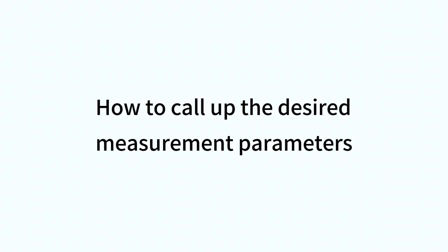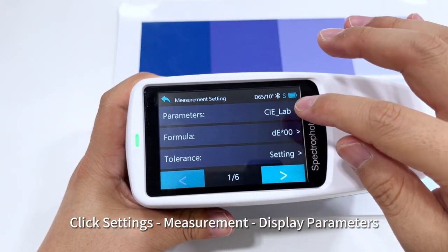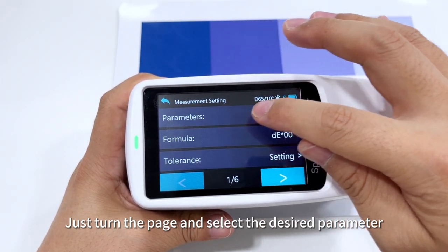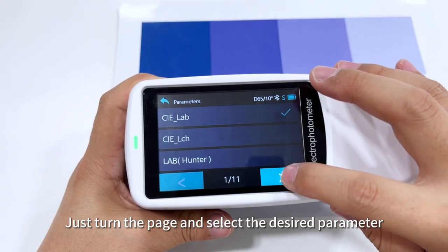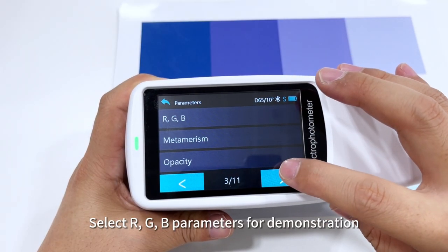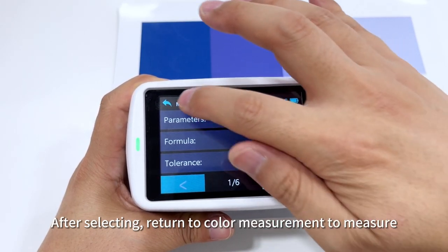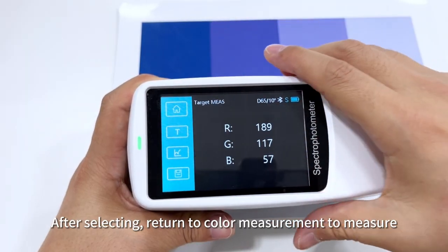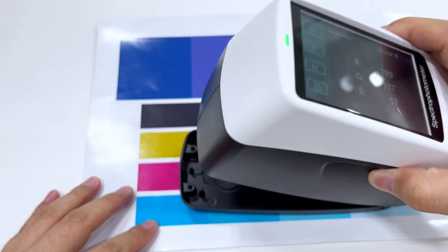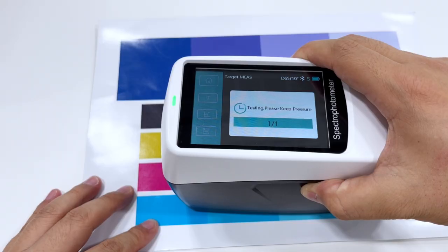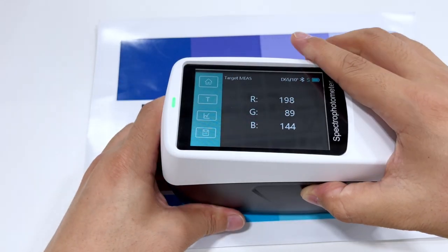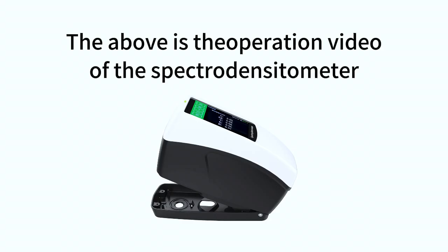How to call up the desired measurement parameters. Click Settings, Measurement, Display Parameters. Just turn the page and select the desired parameter. Select R, G, B parameters for demonstration. After selecting, return to color measurement to measure. The above is the operation video of the spectral densimeter.